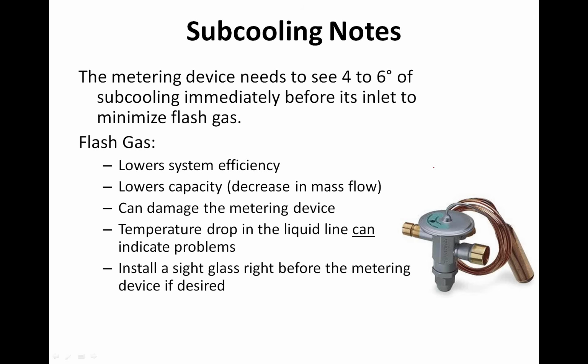You can also install a sight glass right before the metering device if desired. Now, there are two reasons you would do that, and you've got to watch. Sometimes when we have blends of refrigerant, some blends will have some small bubbles in the sight glass, and that's completely normal.